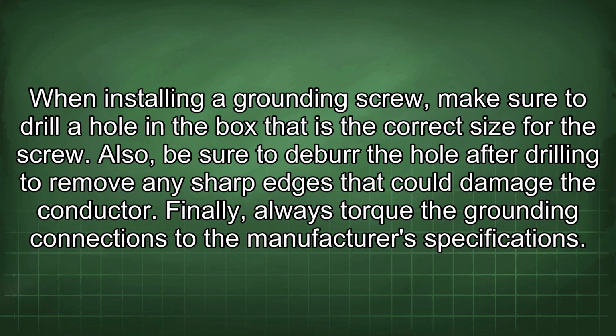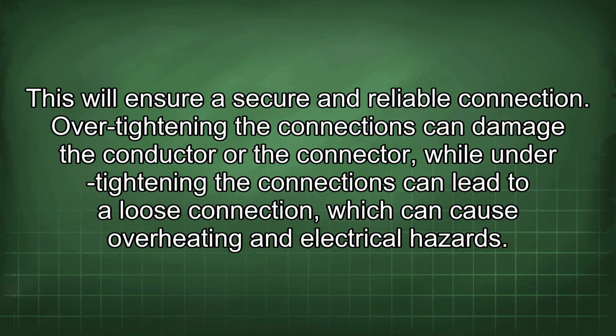When installing a grounding screw, make sure to drill a hole in the box that is the correct size for the screw. Also, be sure to debur the hole after drilling to remove any sharp edges that could damage the conductor. Finally, always torque the grounding connections to the manufacturer's specifications. This will ensure a secure and reliable connection. Over-tightening the connections can damage the conductor or the connector, while under-tightening the connections can lead to a loose connection, which can cause overheating and electrical hazards.